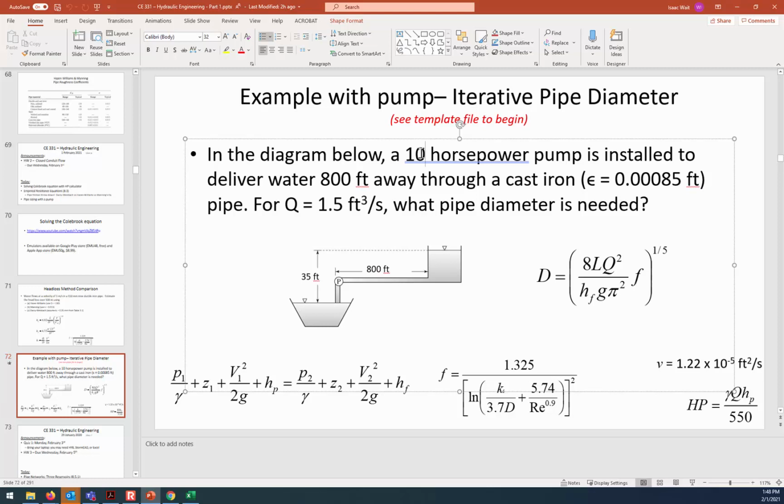If it's okay to pump more than 1.5 cubic feet per second, then you don't need that valve. Like if this was a minimum and you just had to achieve that minimum, then you're golden. But if that's the exact flow rate that's required at all times, then you need a valve downstream of that pump that you can close down because the pump's a little too powerful.